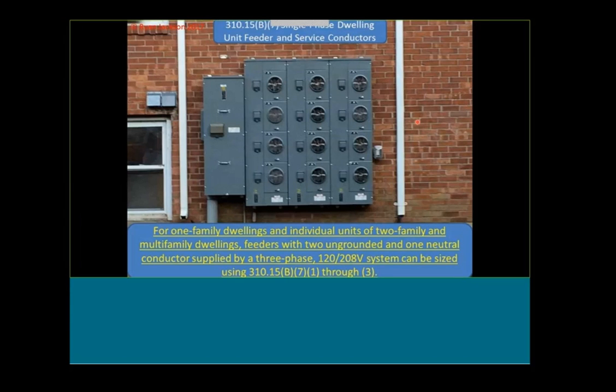This is a change they made in 310.15(B)(7). This is where it says you can use smaller conductors, smaller cables, for certain dwelling units. So the wires coming out of this breaker, feeding the individual units of these apartments or townhouses—that's what this section is talking about. We can use smaller wires for houses and residential than we have to for commercial, because we understand a bit more about load diversity and other factors in residential settings.